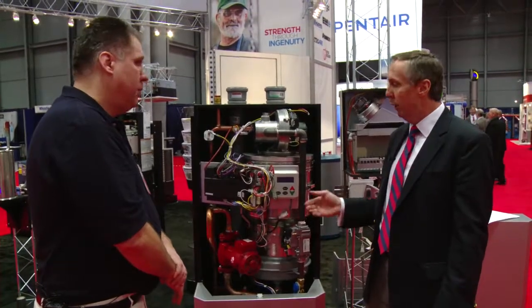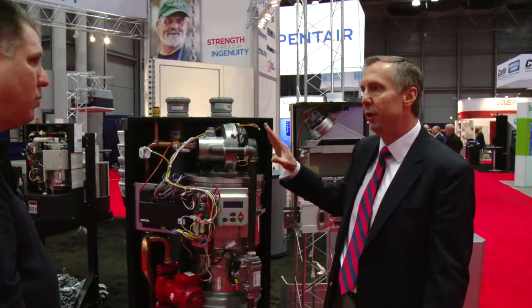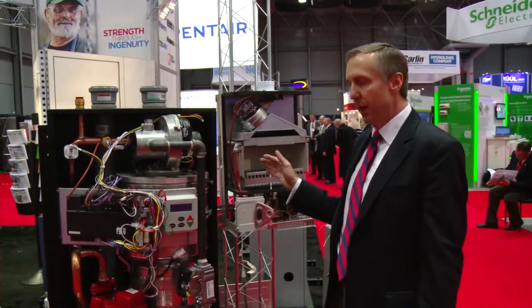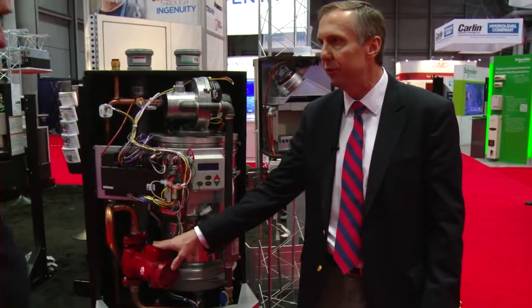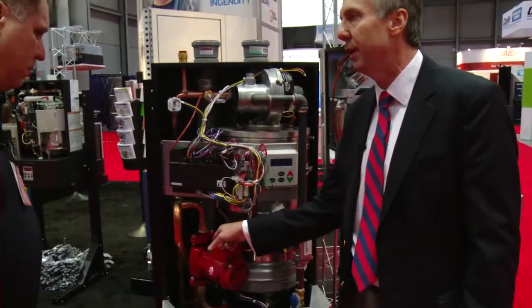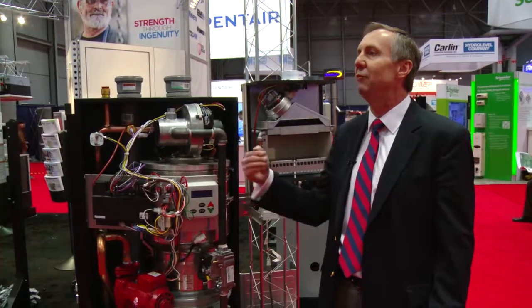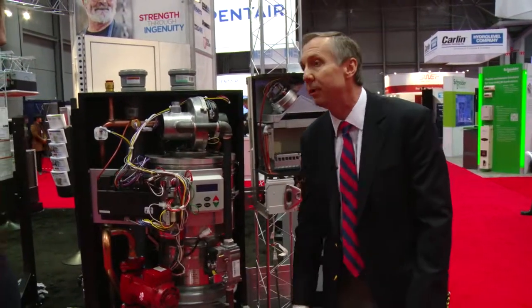Right. Now, you also want to realize that with that type of design, you can then take multiple boilers like this, and because each boiler has its own built-in primary secondary piping system, if you choose to, you can shut off an isolation valve inside the boiler and then pipe primary secondary external if you wanted to put 5, 6 boilers together, thereby saving you the cost of an additional pump. We do that a lot.